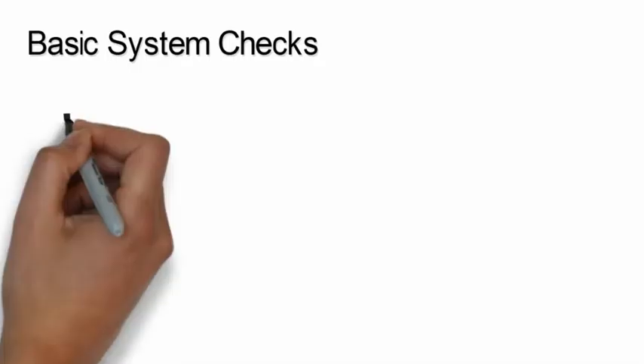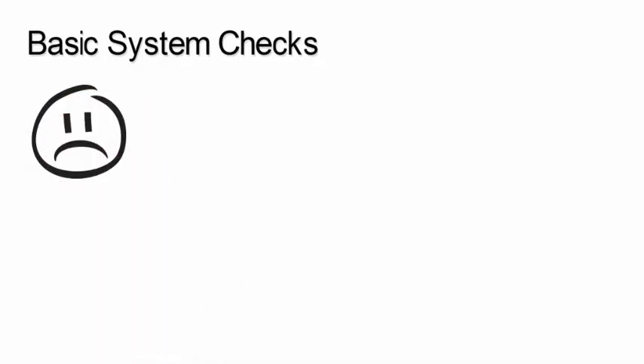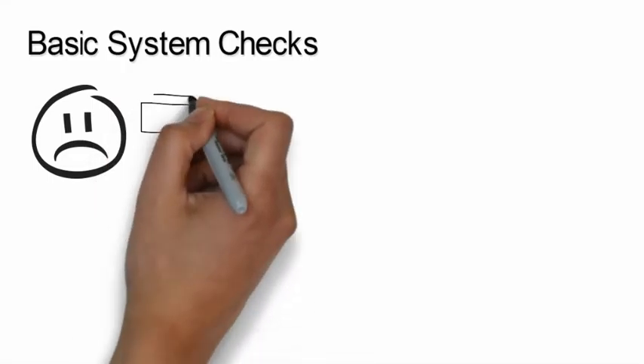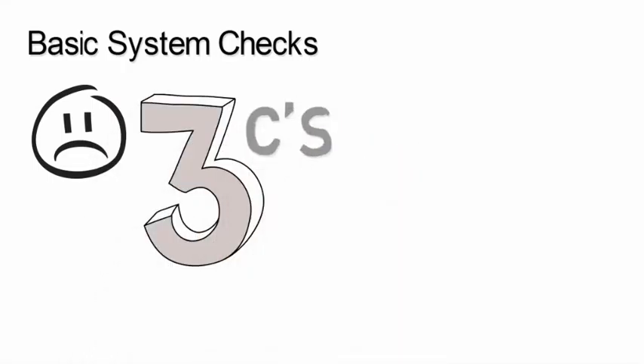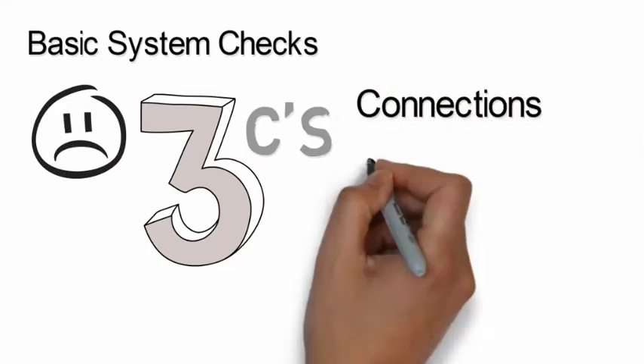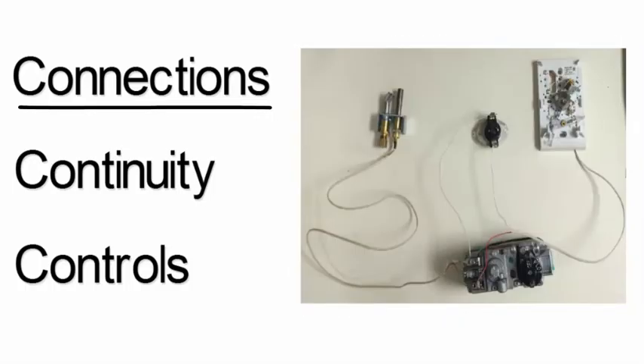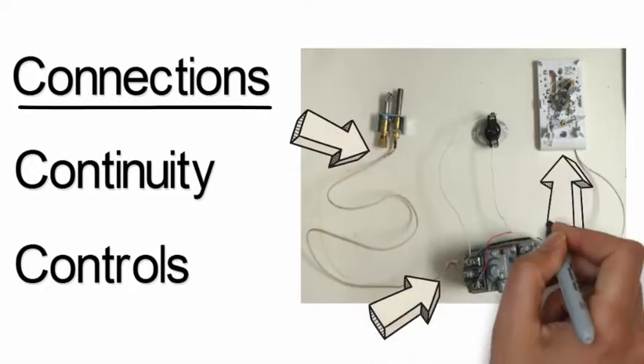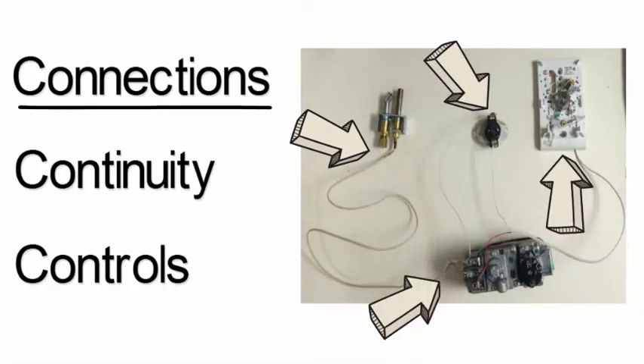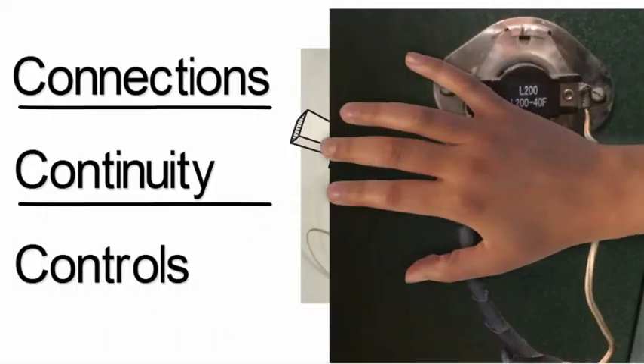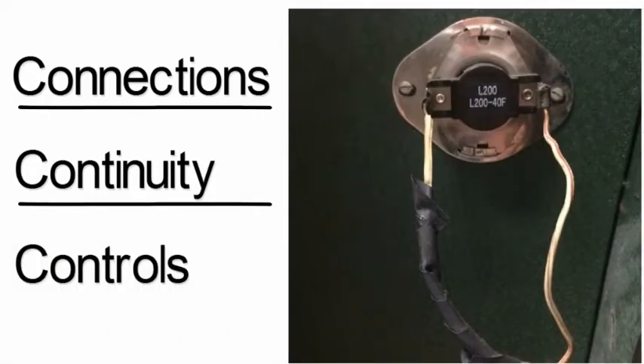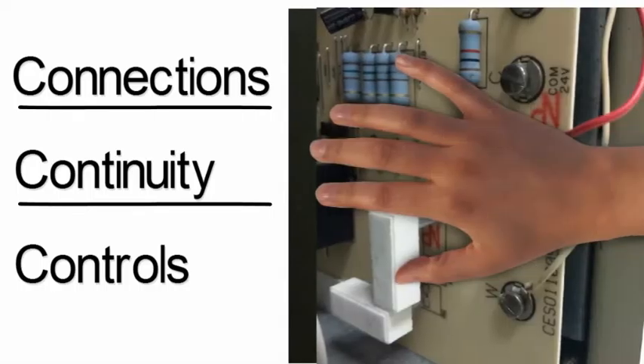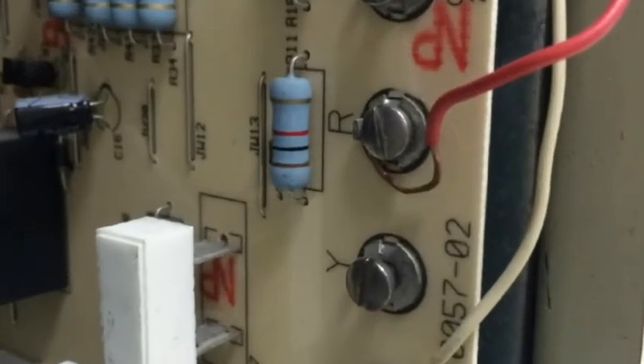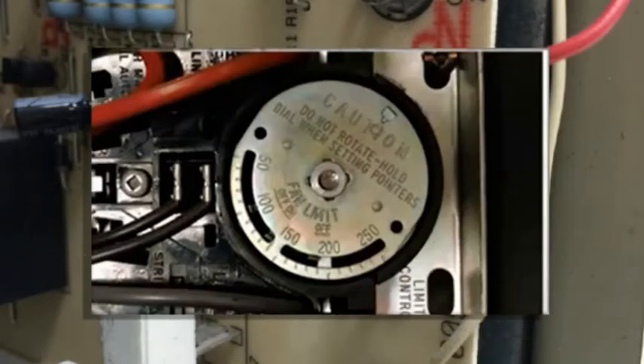Basic system check. Electrical devices do fail, but many problems are caused by something other than a component failure. The 3 C's for a basic system check are connections, continuity, and controls. When checking connections, you must determine that all the components are wired together correctly. As the number of possible connections goes up, the more likely it is that there will be a wrong one. Voltage continuity asks whether all wires and components are good with no breaks and that all terminal connections are solid. It also asks if all switch contacts are conducting as they should.